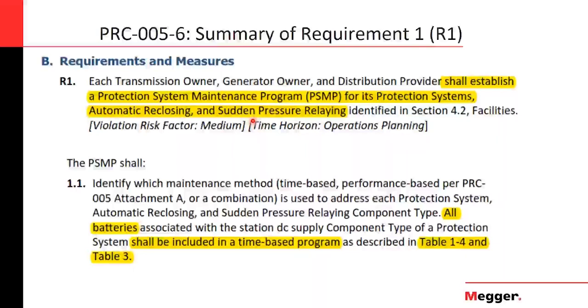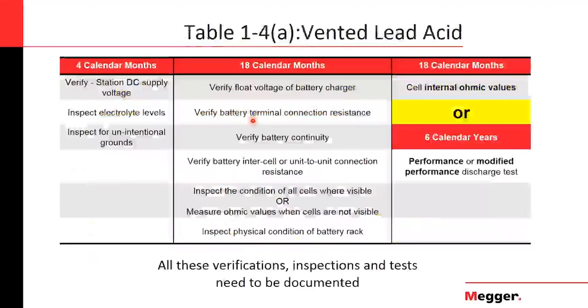they leave you the freedom to decide if you want to do performance-based maintenance or time-based maintenance, or you can do a combination of both. However, for the batteries, it is already established that you need to do what they indicate in this standard. So in a certain way, it's pretty easy to follow. You already have there what is required and its minimum requirements compared to other standards.